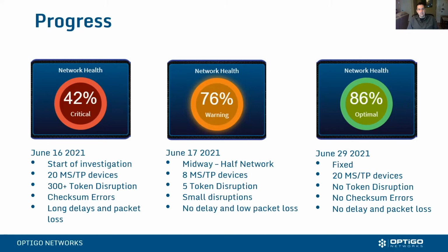So was the system operational at all? Were the pumps still working? Because you said you hardwired them for start stop and all the control. Yeah, all the controls were hardwired. So operationally, we were fortunate in our application in that it didn't affect its day-to-day operation. They still functioned and did the job they were needed to. But if this had been some room control units or some fan coil units, it would have been a whole lot worse, because we'd have had people shouting at us saying, the fan's not on, it's too hot, it's too cold. It could have been a whole lot worse.